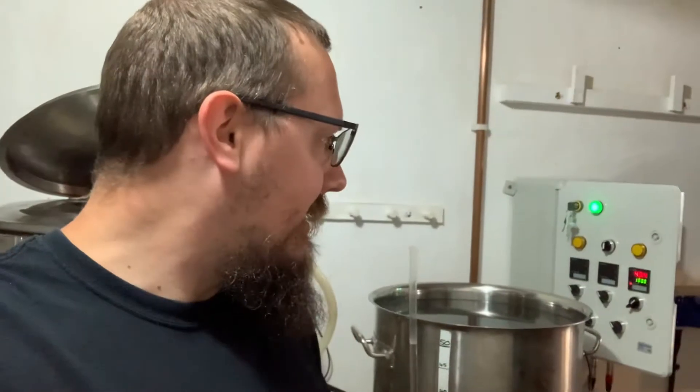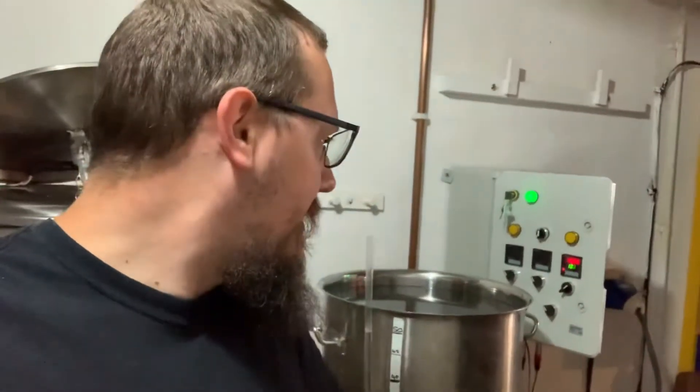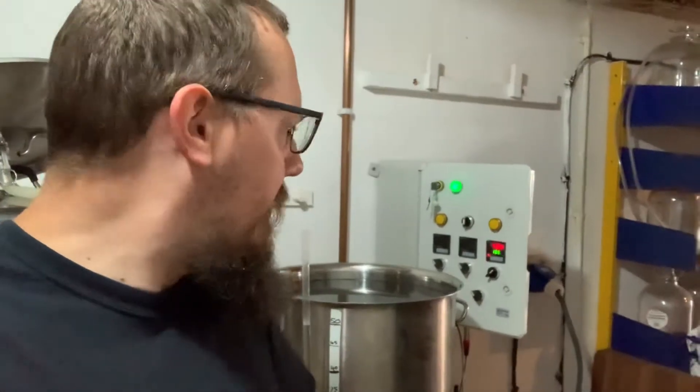15 minutes in and I smelt a little bit of plastic burning. I went in and had a look inside the control panel and one of the bus bars I use on the hot side has melted. Not good — obviously it's pulling a lot of power. I'm sure it was rated for 30 amps, but we'll see.